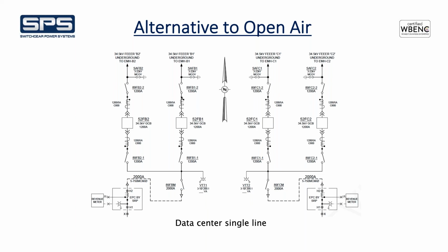Yeah, I can't comment specifically to Powell. I know that many times the integral racking is definitely a cost adder compared to not having it. And I don't know what the premium is that Powell charges for that. But like I said, in the projects that we've compared our metal clad to the metal enclosed design, it has ranged anywhere from about a 10 to 25% savings, depending on different factors. So comparing it to our own metal clad, and I don't believe that we're uncompetitive on the metal clad. So I can tell you that it is about 10 to 25% when we've compared the two.